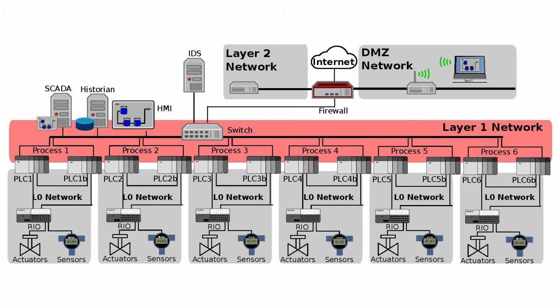In most cases, the PLC is connected to a remote I/O unit, which is going to do the conversion to analog signals to the sensors and actuators. In both the level 1 and the level 0 network, the industrial Ethernet IP protocol is used for communication. This industrial protocol is in particular used by Allen Bradley products. Although the name is Ethernet IP, it's not directly related to Ethernet or IP. Instead, it's running on top of TCP.